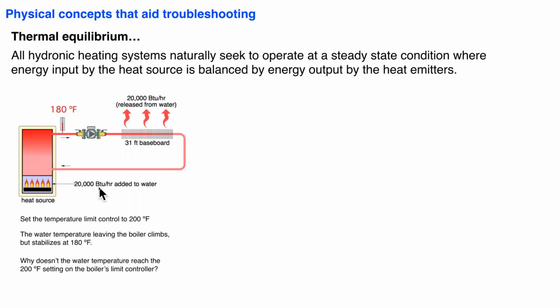And that's an important concept, because sometimes a technician might try to set that high limit on the heat source higher and wonder, why doesn't the heat source get there? Is there something wrong with the heat source? And in reality, no, there's nothing wrong with the heat source. The system just found its natural balance point, okay?